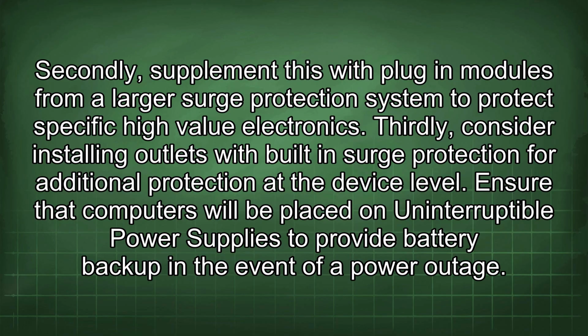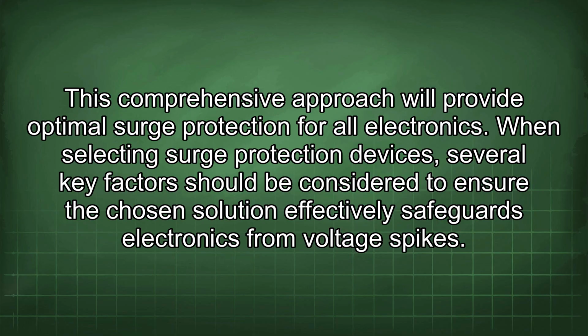Thirdly, consider installing outlets with built-in surge protection for additional protection at the device level. Ensure that computers will be placed on uninterruptible power supplies to provide battery backup in the event of a power outage. This comprehensive approach will provide optimal surge protection for all electronics.